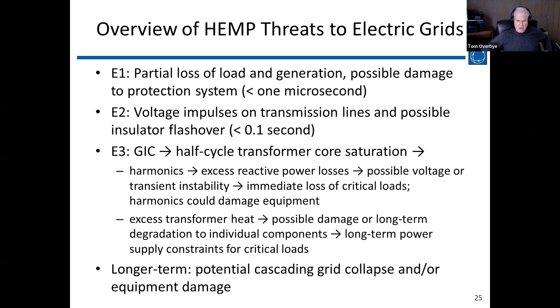On E3, the focus is on causing what's known as geomagnetically induced currents in the grid, or GICs. These GICs are quasi-DC currents. They're slowly varying, with a frequency of much less than 1 hertz. What happens is they superimpose on the AC signal, 60 hertz in this country, and that can cause saturation in the transformers. And when the transformers saturate, they get harmonics. And when they get harmonics, that causes increased reactive power loading in the positive sequence on the transformers, and it can also cause heating damage to the transformer. The focus here is mostly on preventing cascading grid collapse caused by this increased reactive power loading in the transformers. But with HEMP, some people say it could cause heating damage on transformers.